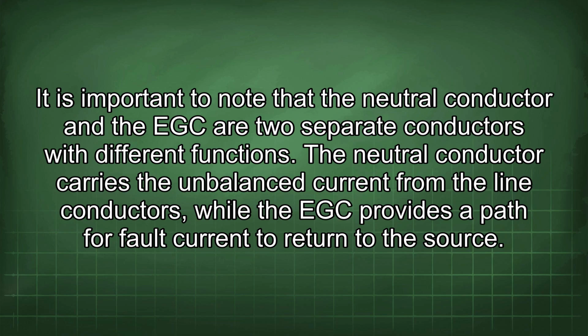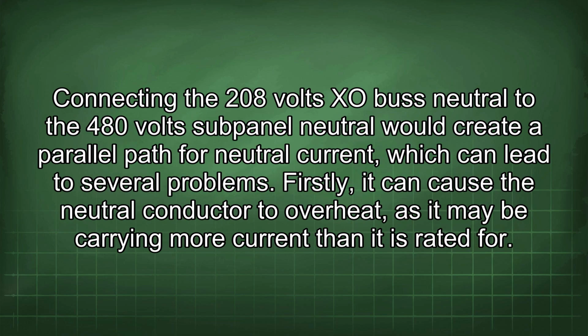The neutral conductor carries the unbalanced current from the line conductors, while the EGC provides a path for fault current to return to the source. Connecting the 208 volts XO bus neutral to the 480 volts subpanel neutral would create a parallel path for neutral current, which can lead to several problems.